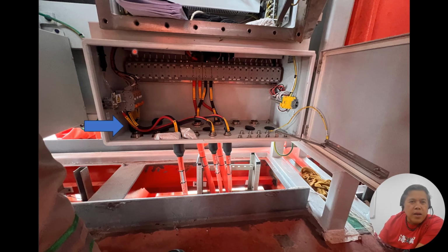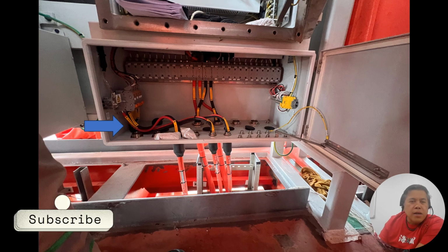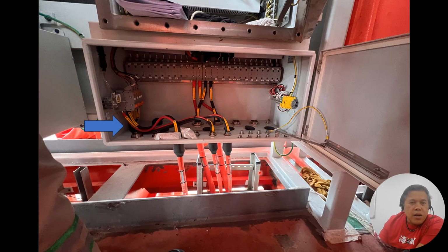This is our compartment of our cables, from the top. This is our main JB, and this is our connection to our field terminals. As you can see here, this is our deck penetration. This is a cutout, and then the cable passes through. And then you can see here, this is the cable tray. It's not sufficient to install the cables, meaning the tray that they installed is smaller. We need a bigger tray in order to accommodate all the cables coming into this compartment.